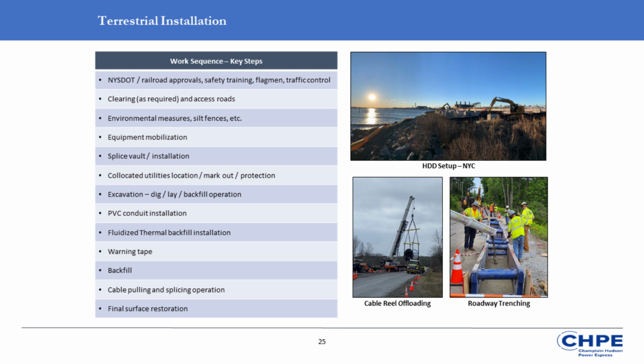Our excavation process, the team calls it DLB: dig, lay, backfill. So we excavate the trench primarily with a conventional backhoe, lay our cables, and backfill with different materials. Our HVDC cables, which are 5-inch diameters apiece, are enclosed in 8-inch conduits, typically PVC. Our primary backfill material is fluidized thermal backfill, which you'll hear us call FTB, a low-strength material with self-compacting properties and specific thermal properties that we specified.